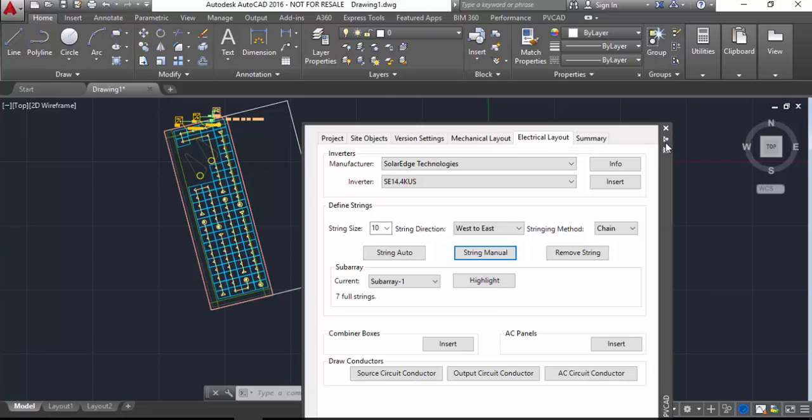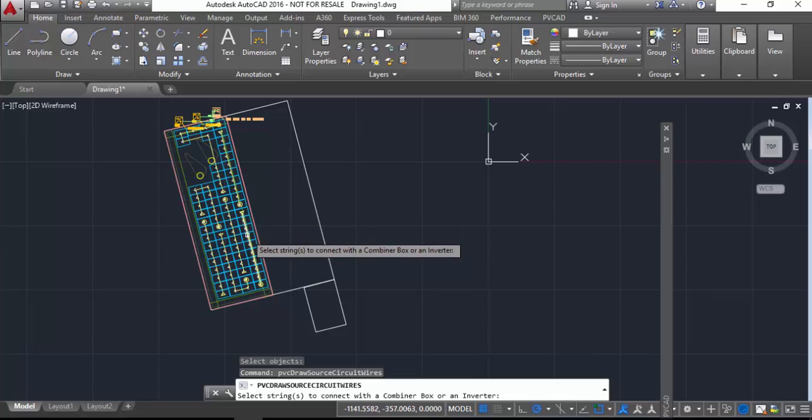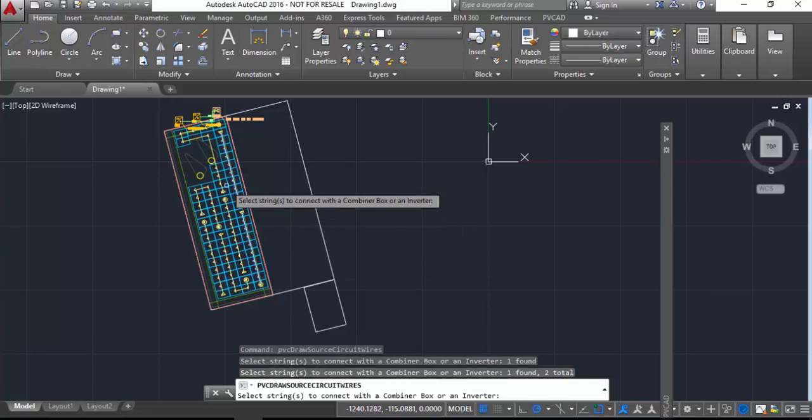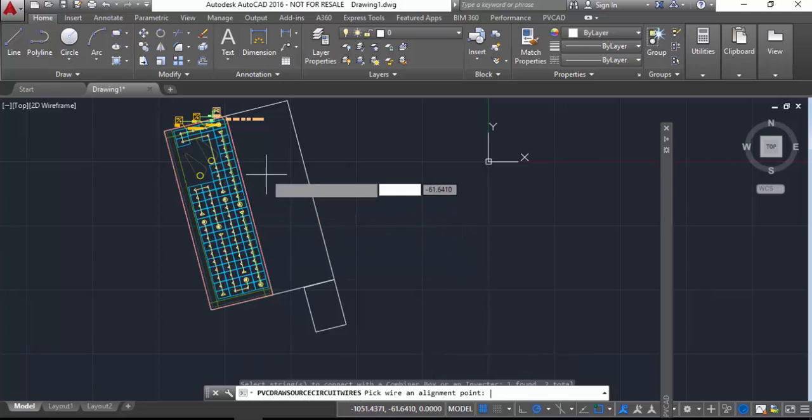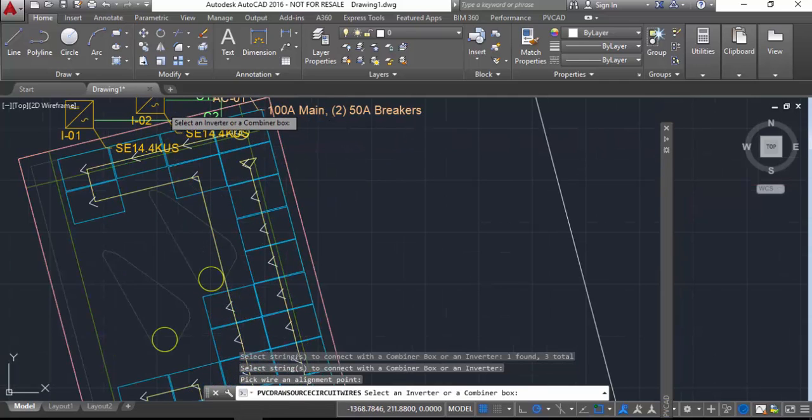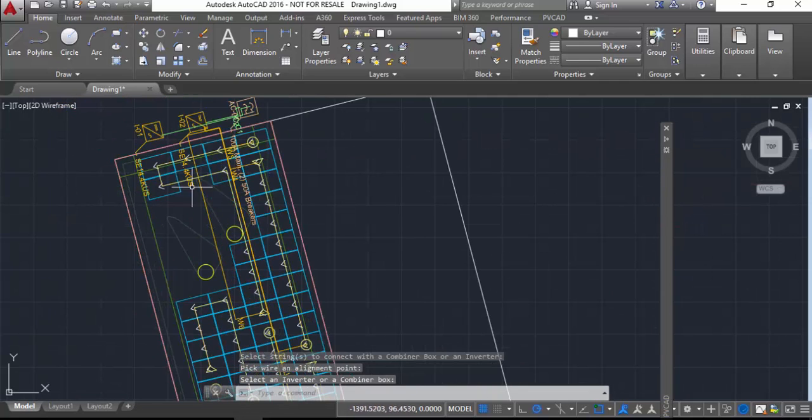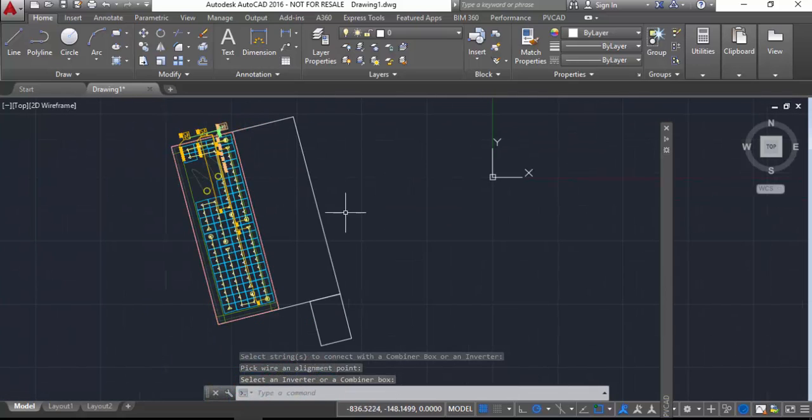Now I'm going to pick, using source circuit conductor, I'm going to pick each group of 10 and click on it and then assign it to one of the inverters. So I select the ones I want, I hit enter, I pick an alignment point, I click the inverter, it puts the wires in between those groups of 10 and that inverter, and I'll do the other one.